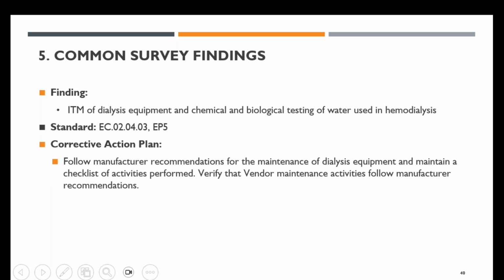The other one, which Lindsay briefly touched upon, is to check with your dialysis department. Most of the time, Biomed doesn't really get into supporting the service component of dialysis, but talk to the departments and make sure who is maintaining your dialysis equipment and where the required documentation is. Is there a way we can obtain that, especially if you are going through a Joint Commission survey? That is very critical. The documentation should also cover the water quality test. We have been noticing that in the past few years: not only the regular maintenance, but they are also looking for the water quality test to be done by the service provider.